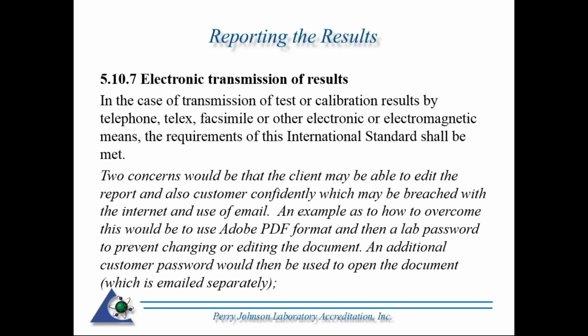An example of how to overcome this would be to use an Adobe PDF format and then a lab password to prevent changing or editing the document. An additional customer password would then be used to open the document. So with doing this, we just don't want to breach any issues with customer confidentiality and the integrity of the test or calibrations that are being reported. We don't want the end user to be able to edit those.